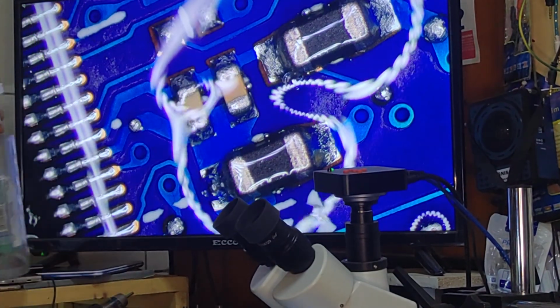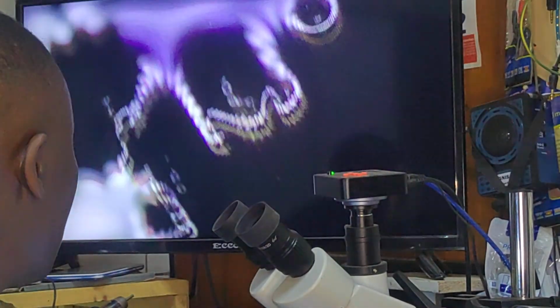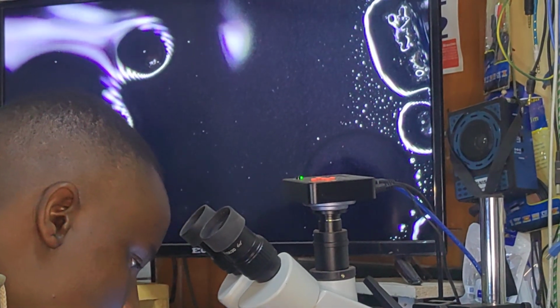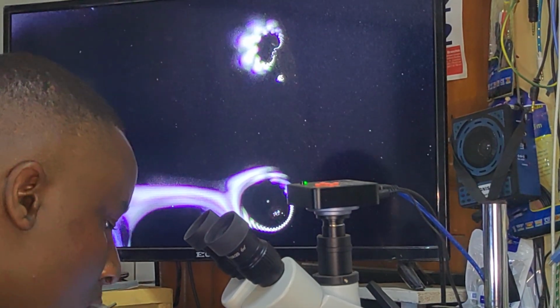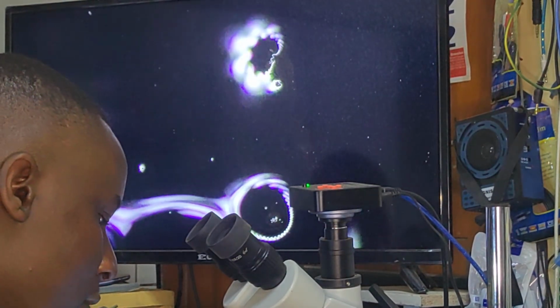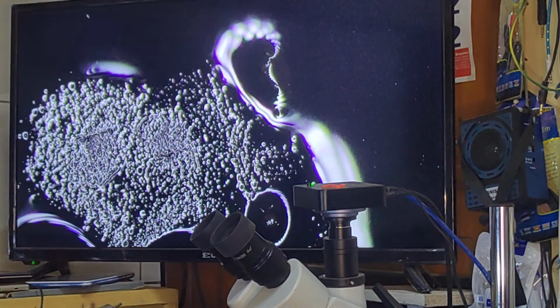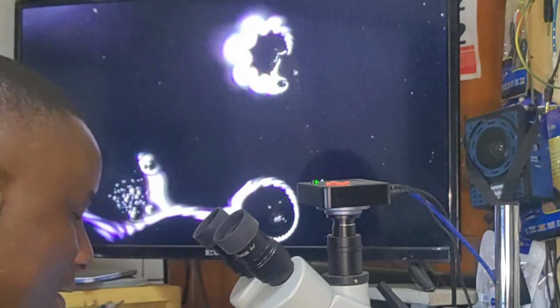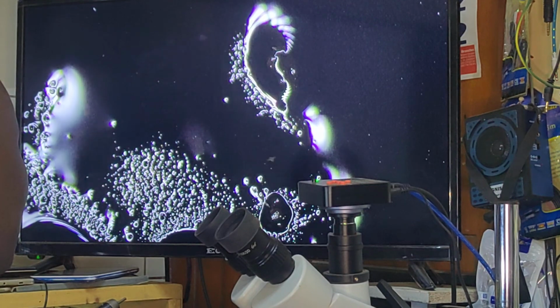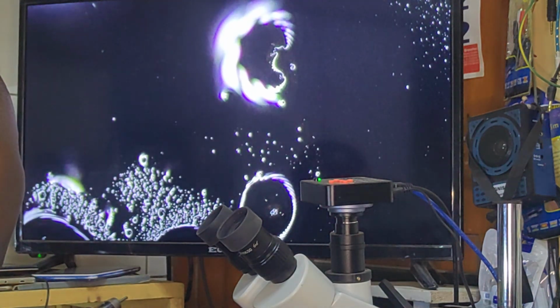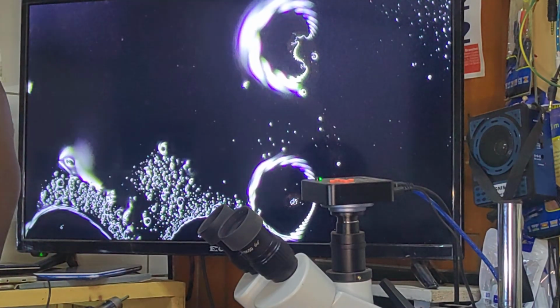Put some alcohol on the chip. That's our chip. Check on the screen of my TV. I release 3.3, then inject 3.3 - you can see. As soon as I inject 3.3, my liquid disappears. If I release, the liquid comes back together, then it disappears again. So what does that mean? It means our controller is dead. That's fault number two.